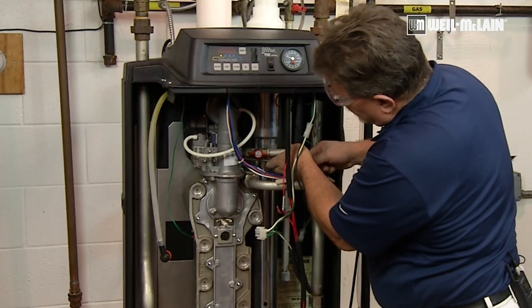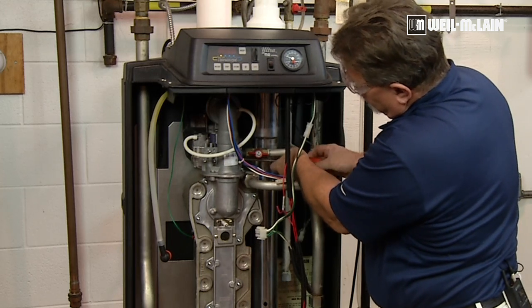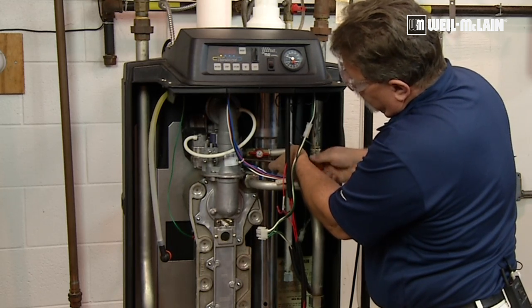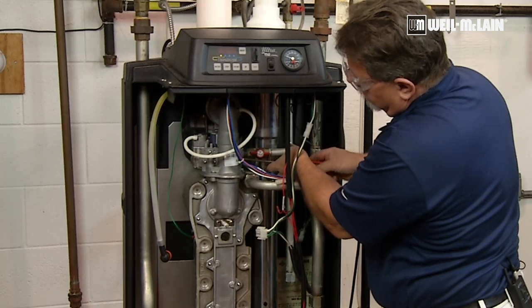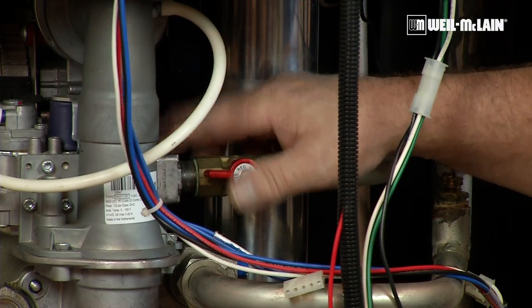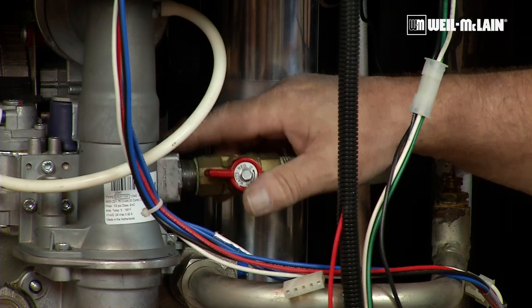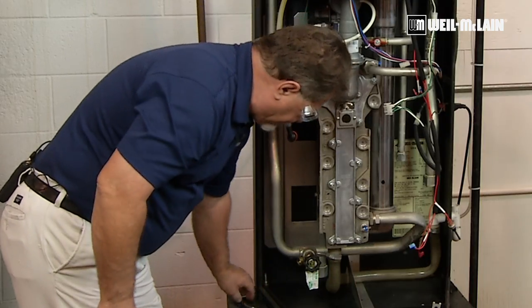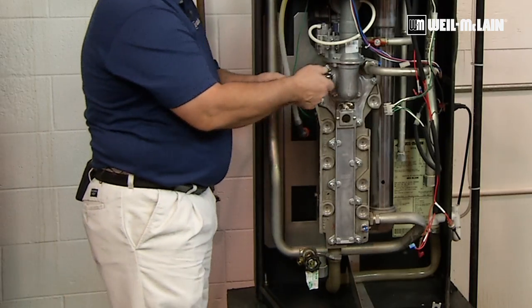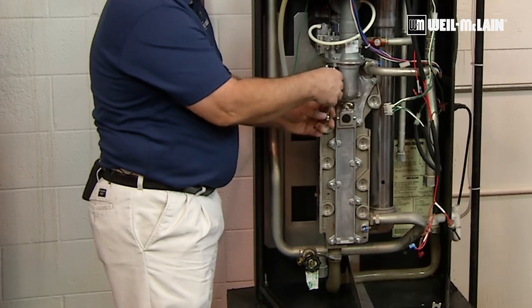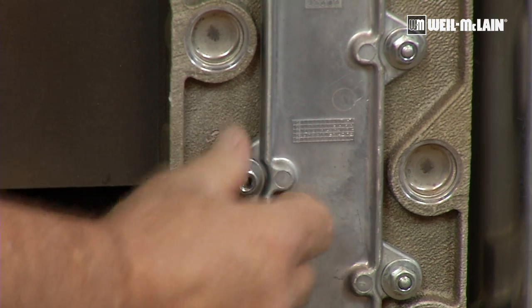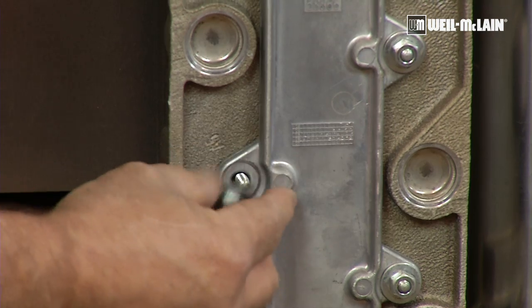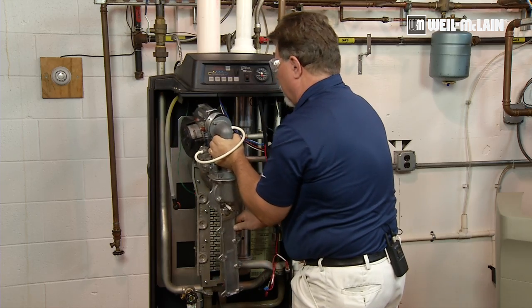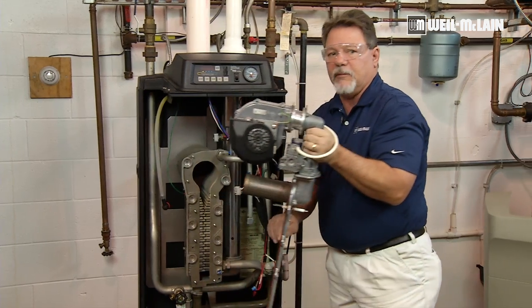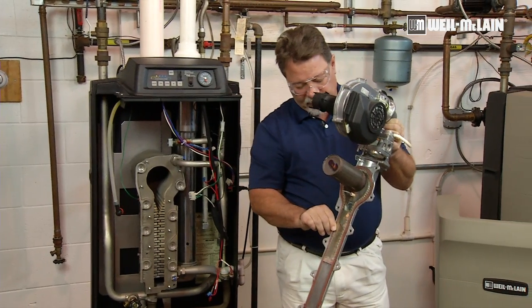So after the wires have been disconnected, the next step then would be removing the gas valve from the manifold piping, and we'll do that at the adapter block. The next step then would be to loosen the nuts from the studs on the heat exchanger and remove them. Now we just gently pull the whole assembly out towards us.